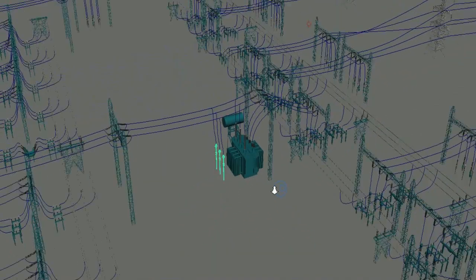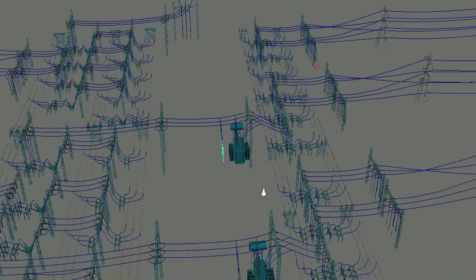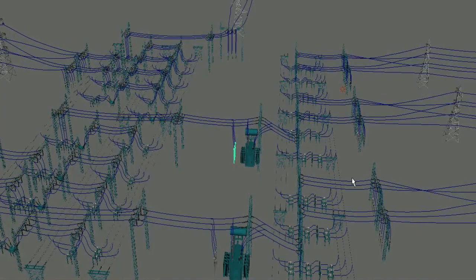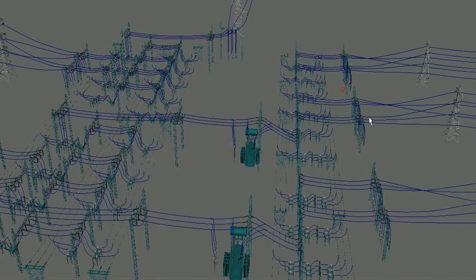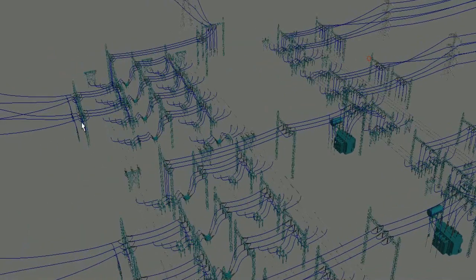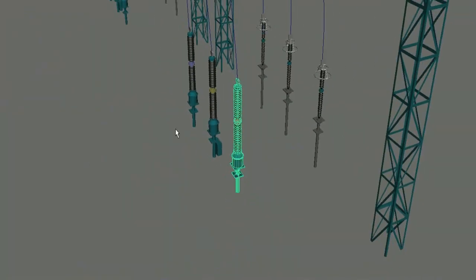These switching surges must not travel up to the neighboring substations, and the switching surges produced there must not enter into these substations. So for that, every substation consists of surge arresters at entry and exit points.